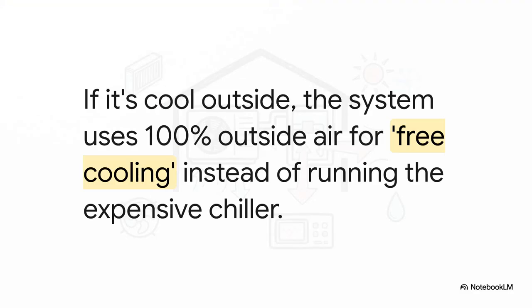And maybe the cleverest strategy of all is the economizer mode. The BMS is always watching the weather outside. If it's a beautiful, cool day, say 55 degrees, why on earth would you spend a fortune running that giant chiller? You wouldn't. The system is smart enough to just open the dampers and use all that free, cool air from outside instead.